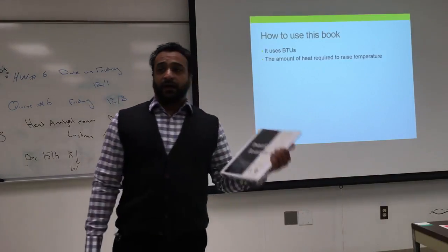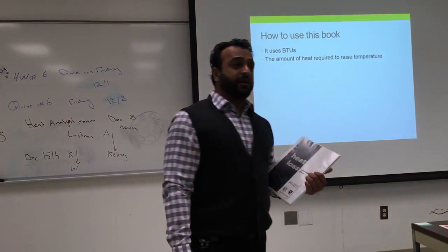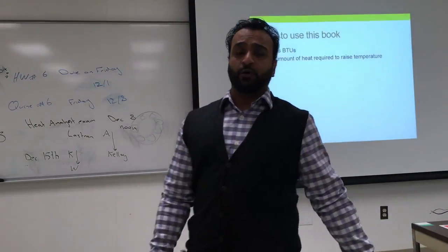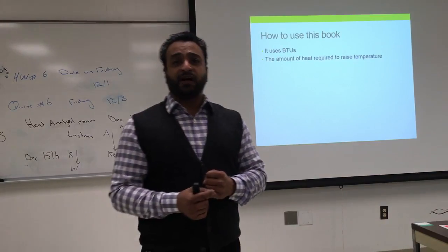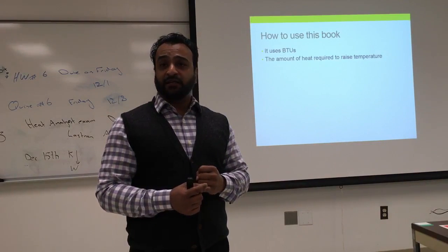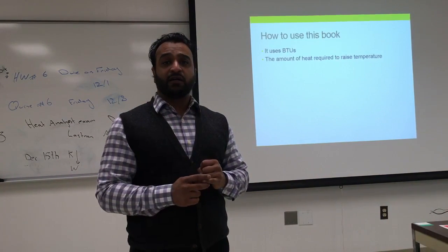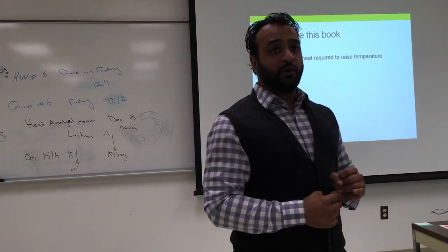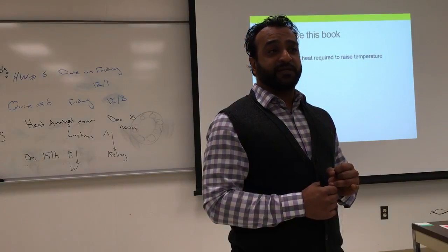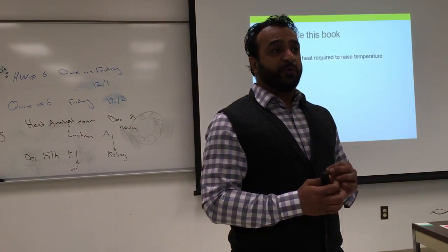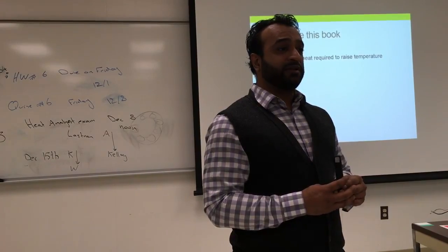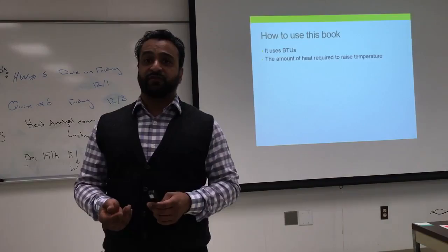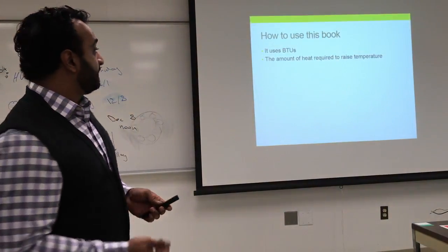So again, the information used from this book, which means the material, specification, the U factor, is going to be the same. You can use the same thing for cooling. However, this time you only factor in solar heat gain if you don't have shades and you don't have low emissivity windows, and if you have overcrowded living space. And light bulbs, we used to add them in the heating load, but not anymore because now everybody's using CFLs or LED, which are not really that much of a heat addition.